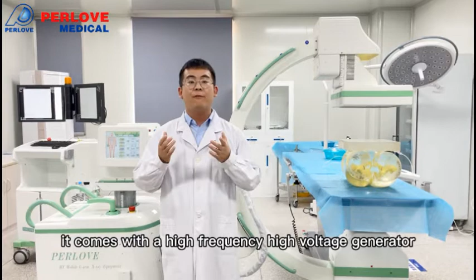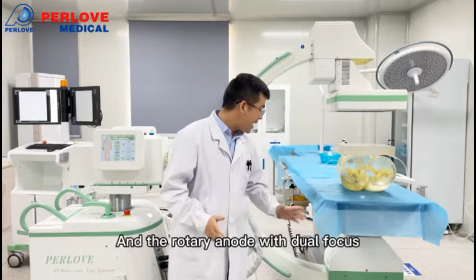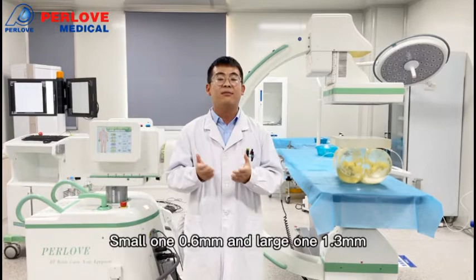First, on the one hand, is the powerful image chain. This machine comes with a high-frequency, high-voltage generator with 25 kW output power to ensure a more stable and high-quality X-ray source from the very beginning. The rotary anode has dual focus, the small one 0.6 and the larger one 1.3 millimeters. The thermal capacity can reach 1000 kilojoules, so it can meet high-intensity exposure needs and ensure long-time interventional surgeries are performed successfully.